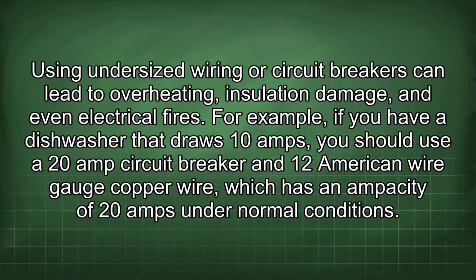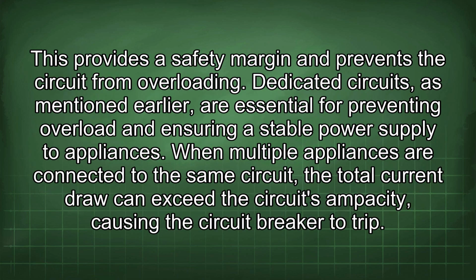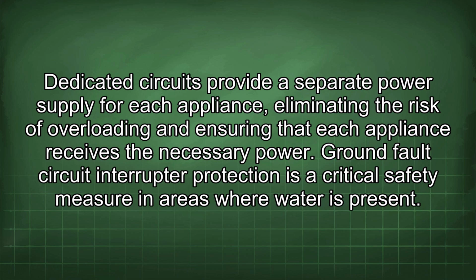For example, if you have a dishwasher that draws 10 amps, you should use a 20 amp circuit breaker and 12 American wire gauge copper wire, which has an ampacity of 20 amps under normal conditions. This provides a safety margin and prevents the circuit from overloading. Dedicated circuits, as mentioned earlier, are essential for preventing overload and ensuring a stable power supply to appliances. When multiple appliances are connected to the same circuit, the total current draw can exceed the circuit's ampacity, causing the circuit breaker to trip. Dedicated circuits provide a separate power supply for each appliance, eliminating the risk of overloading and ensuring that each appliance receives the necessary power.